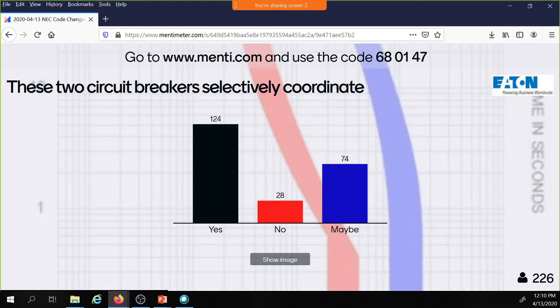I don't care if you don't feel that three-phase bolted fault current is a realistic number to selectively coordinate to. You have to pick some other value of fault current. I used to fall back on the arcing current. IEEE Red Book would publish a certain percentage of the bolted fault current. I'd fall back and say that I selectively coordinate for the most common fault current, which is the arcing ground fault, which IEEE would typically publish a percentage value. But in any case, you really need to know fault current.